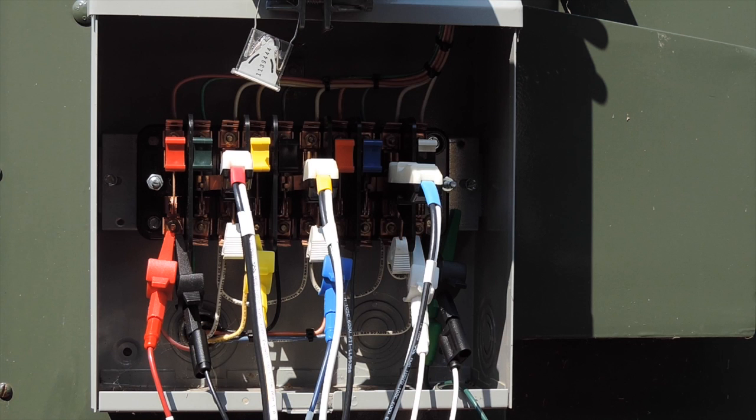The next step is to begin your secondary connections at the test switch. You're going to connect phase A, B, and C voltages along with neutral to their respective tabs. Then you're going to shunt the test switches for your CTs, open the connections that your CTs are going to go into for your doughnut CTs, and once they are inserted into the test switches, reclose your shunts. This will allow current to begin to flow again.